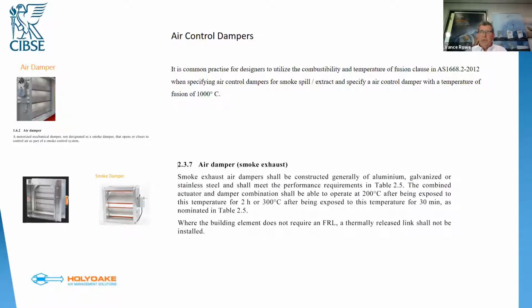And because the dampers are supported from axles at either end, you'll find that a large part of the damper blade is actually unsupported when it's in use. I tend to push people towards aluminium dampers where possible. We find that we get a better seal with the aluminium damper.